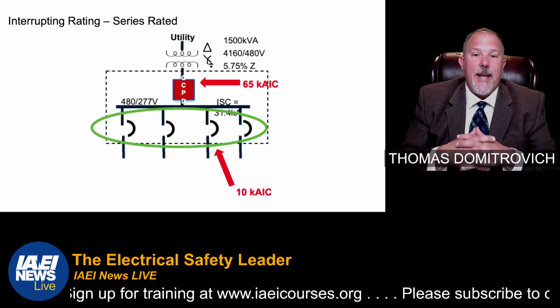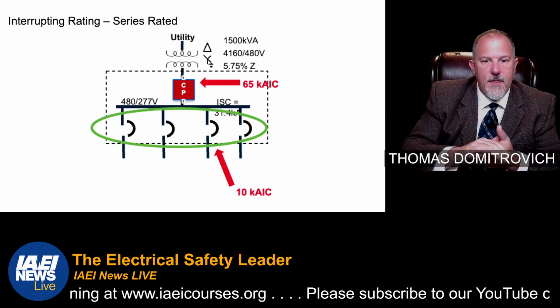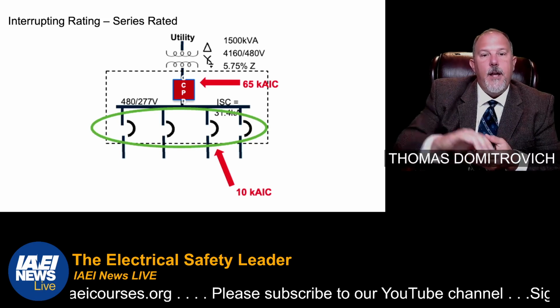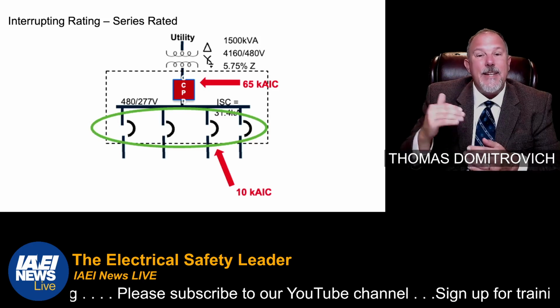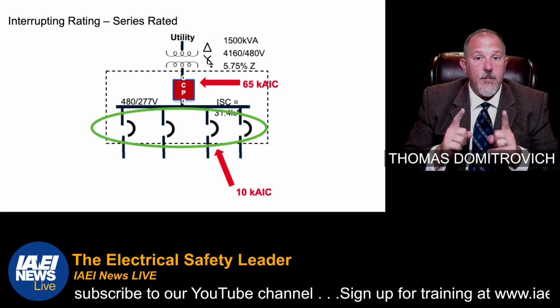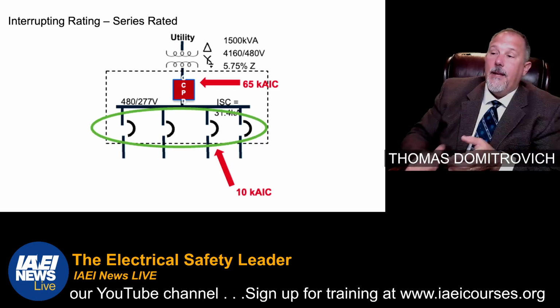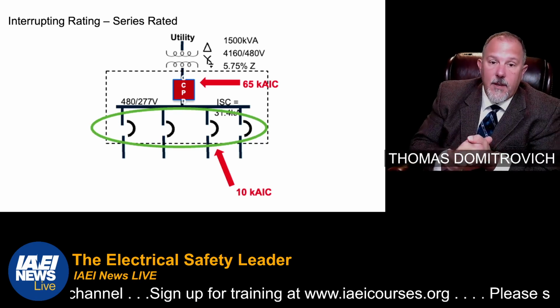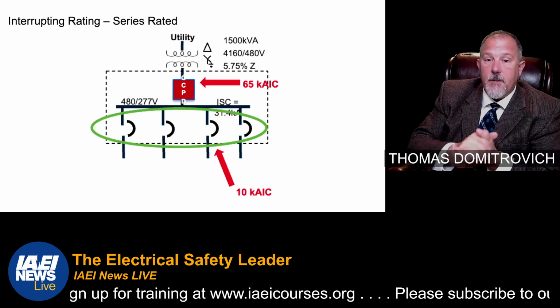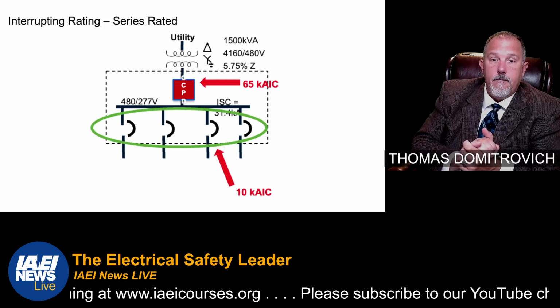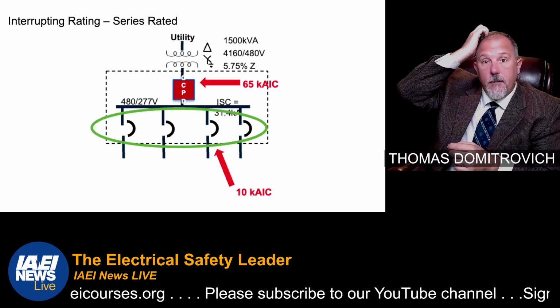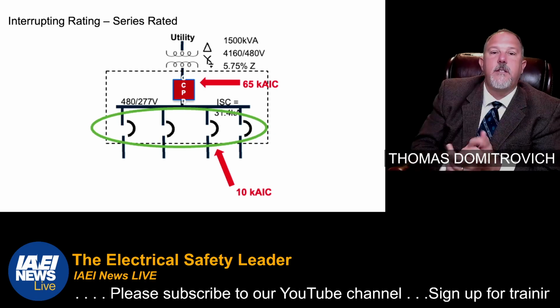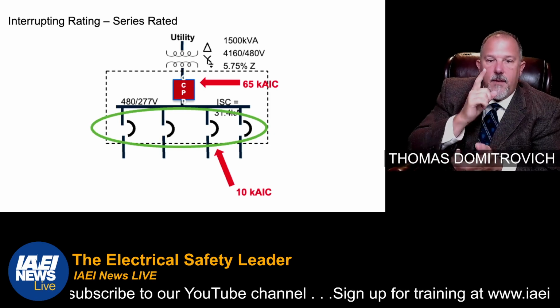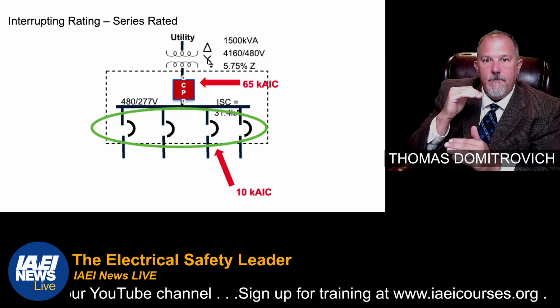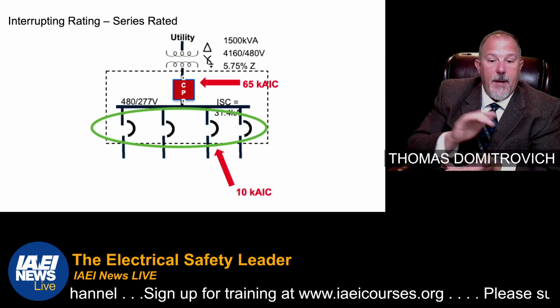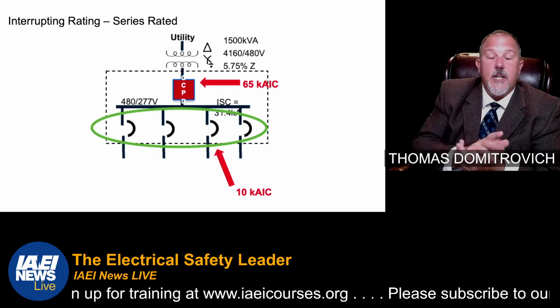This is a series rated system. I have 31,000 amps of available fault current. I have a 65K breaker upstream. I've only got a 10K breaker downstream. If I were to enforce the code, I would say that 10K breaker cannot interrupt 31,000 amps. So I have to remove it and put something greater than 31,000 amps there. Maybe a 42K would be a fully rated system, where all of the overcurrent devices can clear the fault current.